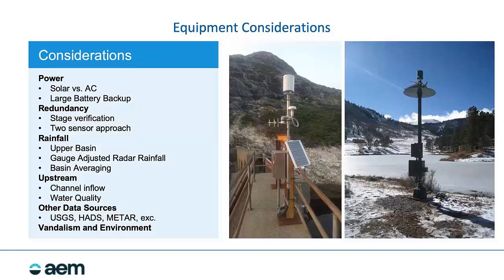Rainfall, we touched on this a little bit earlier, but if you have a large watershed that all contributes into your reservoir and is highly affected by rainfall in the upper basin, adding additional rain gauges to understand -- we got an intense rainfall, half an inch in 15 minutes -- what does that correlate to what's going to be coming down into your basin, into your watershed. That way we can alarm early on that criteria before that water actually hits your reservoir, and that goes upstream too.